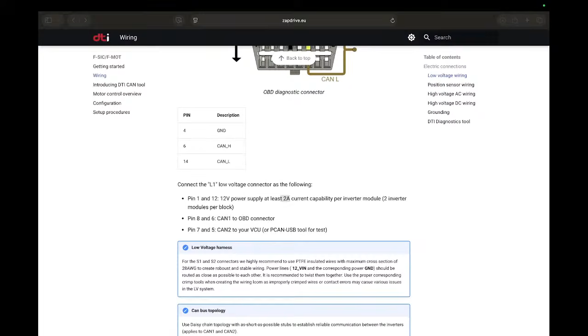Also, you need to make sure the inverter is capable of using 28 AWG wires, as I mentioned formerly. That means you need to provide a separate power supply for each inverter - you cannot daisy chain the connections. The best principle is to use star point topology for the groundings, and dedicated wires for the positive wires of the low voltage power supplies. There are multiple positive connection points on the inverter. This specific quick start guide does not mention it, but there are multiple ones.